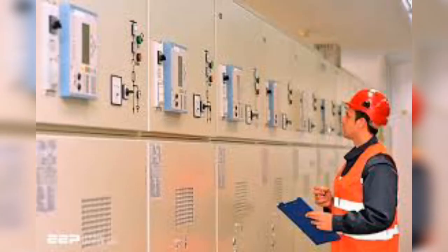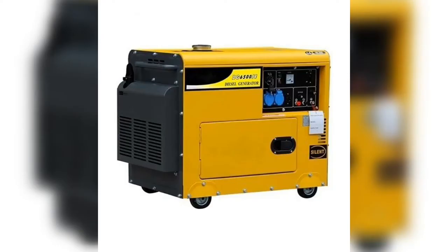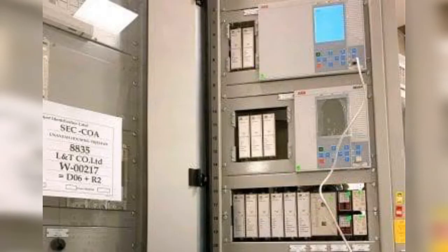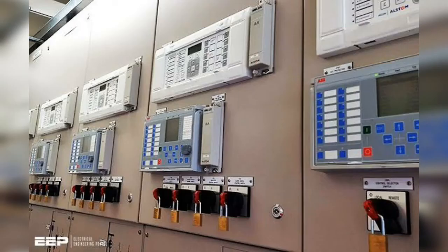How does generator differential protection work? Differential protection is provided for the generator by using longitudinal differential relays, generally continuously energized armature type relays. These relays are used for this purpose because they operate at high speed and are free from being affected by AC transients in power circuits.